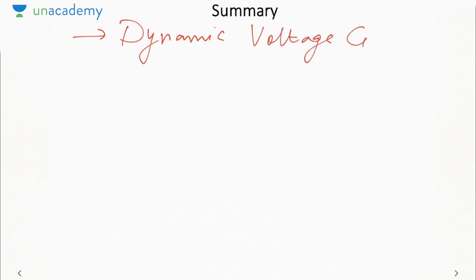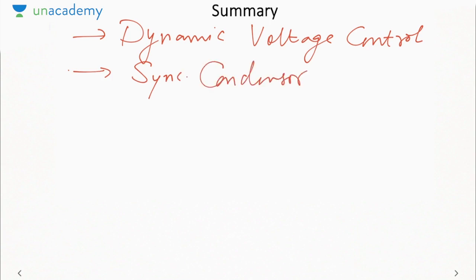So let us summarize what we covered in this lecture. We first saw dynamic voltage control. What does that mean? So I told you, whenever we do the voltage control with the help of synchronous motor, it is termed as dynamic voltage control. Then I told you about synchronous condenser, which is the overexcited synchronous motor at no load condition. Then we saw synchronous coil that works as a shunt inductor. It is a no load synchronous motor running under excited condition.